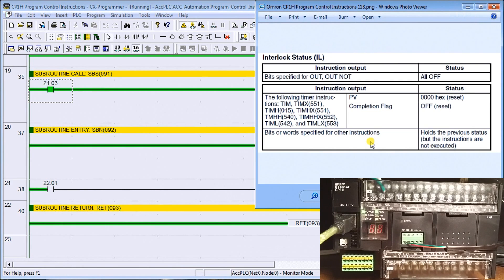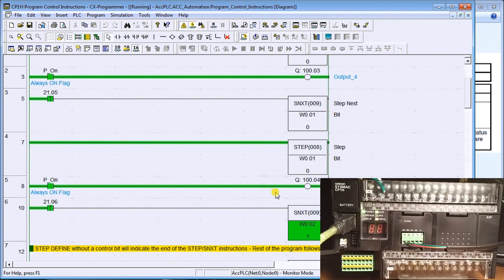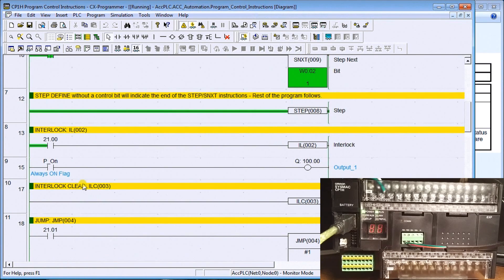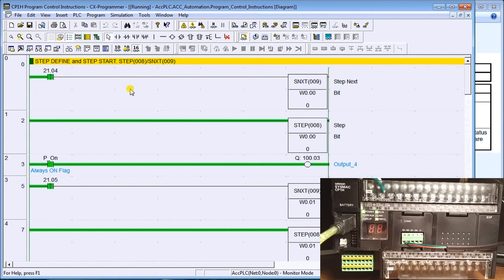The step instruction has to appear at the start of your program. Looking at the start of our program, we have the step and step next. I've got a couple of different bits we're controlling here — output 100.03 and output 100.04. The next step then releases that to the rest of the program. If we have a step without a defined control bit, it indicates the end of the step/step next instructions, which is why we stick it at the front of the program. When I energize this step, it goes to this word through bit 0 and starts scanning this area to set output bit 100.03.